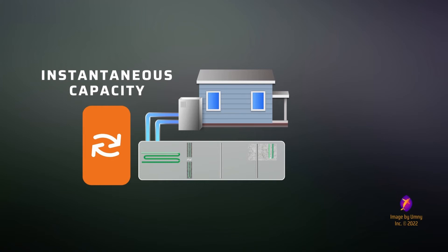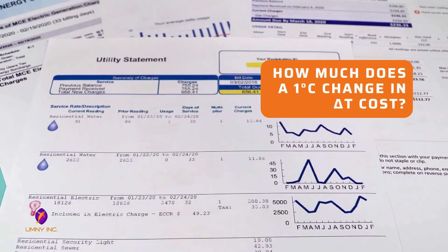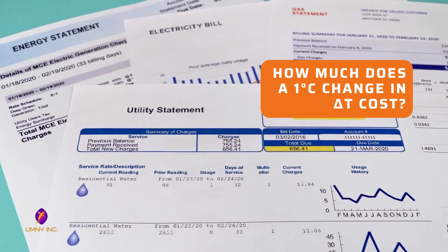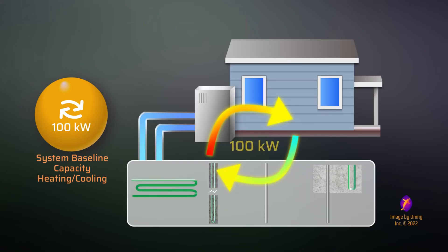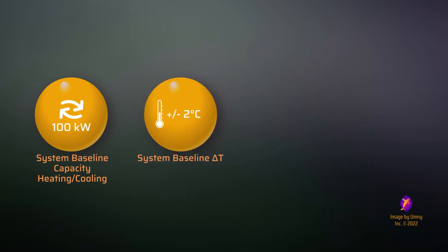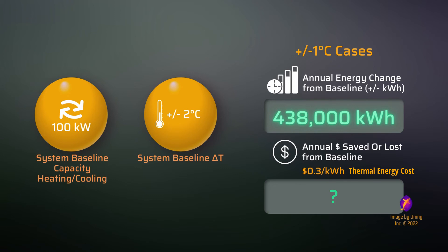Until this point, we've been focusing on instantaneous performance changes. But how do these effects add up over the course of a year of operation, and what is the resulting cost or savings from a plus or minus 1 degree change in delta T? If we have a geothermal system sized for 100 kilowatts of capacity — approximately 28 tons — it can produce 100 kilowatts of peak heating and cooling energy. While operating with a small baseline delta T, a change of just 1 degree results in 438,000 kilowatt hours, or nearly 1.5 billion BTUs, across the year. If our energy cost is 30 cents per kilowatt hour, this means we could be saving or losing a total of $131,400 across the year.